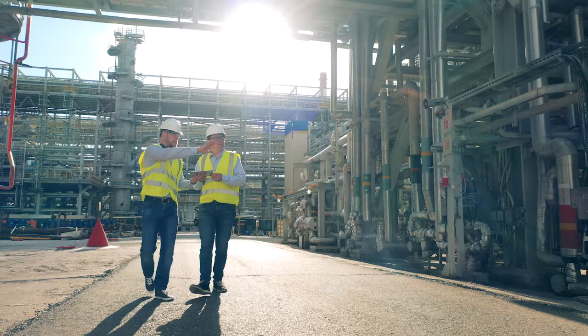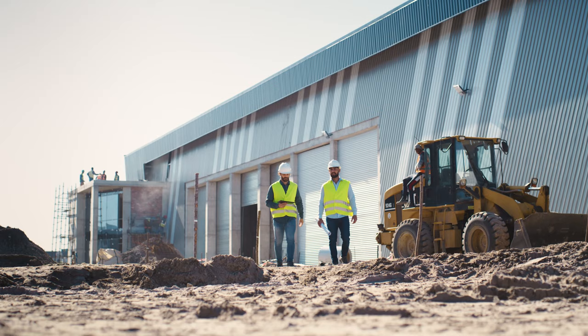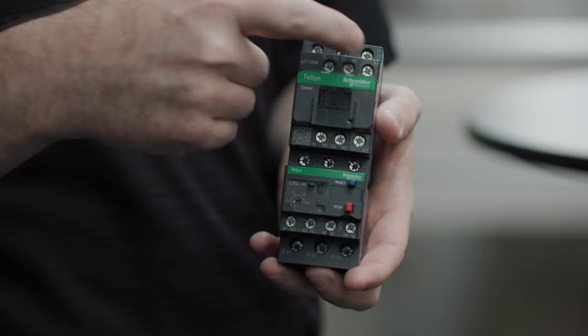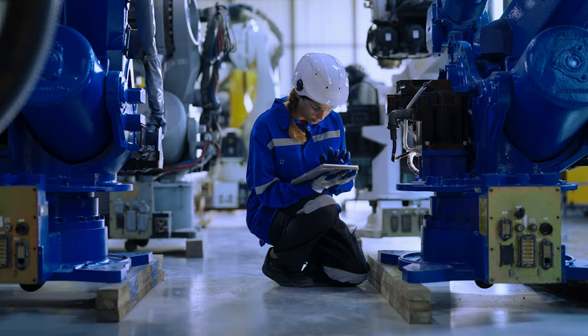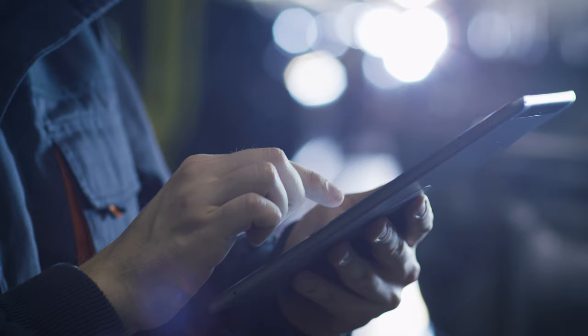For end users, this really enables them to increase their workforce productivity. System integrators are always under the pressure of project timelines and making money on the project — TeSys Island gives them a unique way to wire, configure, and commission the panel. A lot of the wiring with traditional motor starters going from the PLC to the contactor, to the coil, to the auxiliary contact, the overload — all that goes away. Now we're using a ribbon cable connection, click click click, and on the commissioning side there's an operation and maintenance tool which allows them to easily see what's going on as they start up the machine and make adjustments within TeSys Island without having to mess with the PLC program.